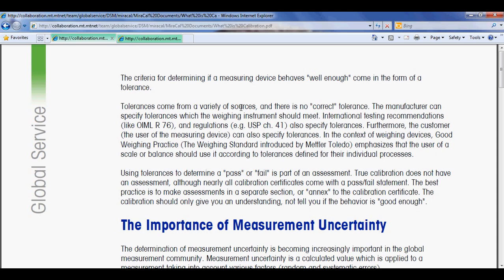The manufacturer can specify tolerances for which the weighing instrument should meet. We do that at Mettler-Toledo for all of our lab balances. We have manufacturer tolerances. International testing recommendations like the OIML R76 and regulations such as the USP General Chapter 41 also specify tolerances. Furthermore, the customer can also specify tolerances. And in the context of weighing devices, the good weighing practice, the weighing standard introduced by Mettler-Toledo, emphasizes that the user of a scale or balance should use it according to tolerances defined for their individual processes.